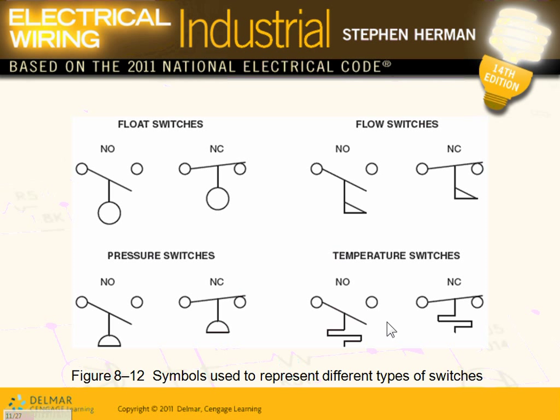Here are your input devices. Floating switch — this is normally open. If the water starts pushing the float up, this contact will close. These are your so-called input devices. Without input devices like these mechanical, physical devices, you can't understand the control system. Float switches, normally open and normally closed. Pressure switches — if pressure builds up here, this will close; if pressure builds up at the other point, this will open.